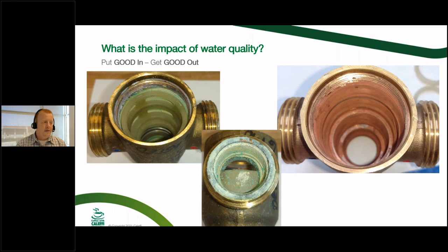So don't think that the mixing valve is just completely impenetrable when it comes to scale and debris, okay? Don't think it's bulletproof. We make our mixing valves at Caleffi to withstand corrosion and scaling as best we can, but I've never met a completely 100% bulletproof mixing valve, okay? They're all going to have a point where it's not gonna work anymore. They can no longer go on, okay? And in some cases it's a few years, in some cases it's 10 years, and in certain cases like this one, it was 6 months. Okay, and you can probably see it right here, and then over here 6 months.